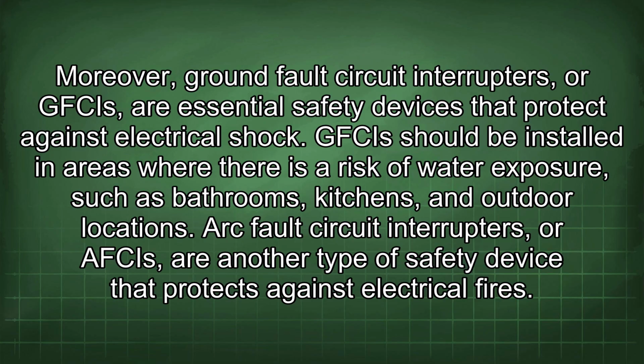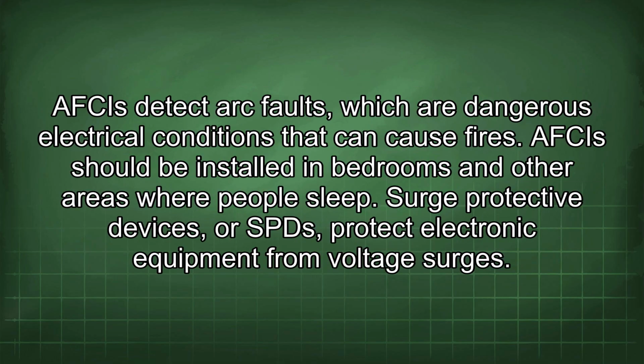Moreover, ground fault circuit interrupters, or GFCIs, are essential safety devices that protect against electrical shock. GFCIs should be installed in areas where there is a risk of water exposure, such as bathrooms, kitchens, and outdoor locations. Arc fault circuit interrupters, or AFCIs, are another type of safety device that protects against electrical fires. AFCIs detect arc faults, which are dangerous electrical conditions that can cause fires. AFCIs should be installed in bedrooms and other areas where people sleep.